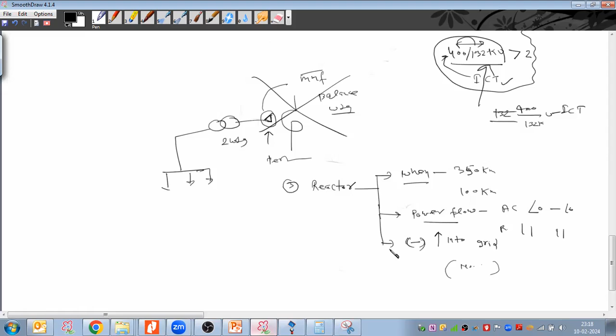And then we discussed the reactor connection in the substations. So we discussed that there are two kinds of reactor connection possible. It could be connected with the line in the center, or it could be connected with the bus bar in the center. And then we discussed that if the reactor is connected with the line, then the reactor must have an NGR. This NGR is not neutral grounding resistance. This NGR is for the neutral grounding reactor. Why is this reactor required? Because it is required for single pole auto reclosing, to provide the facility of single pole auto reclosing of the circuit breaker, and to minimize the transient recovery voltage in the circuit breaker.